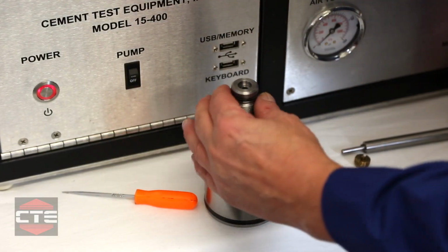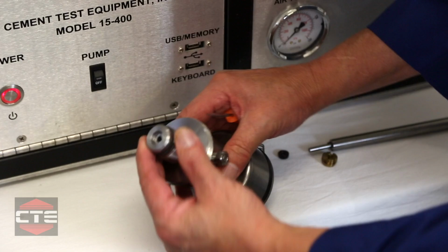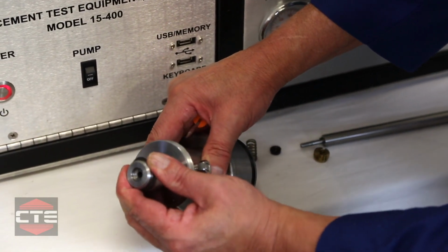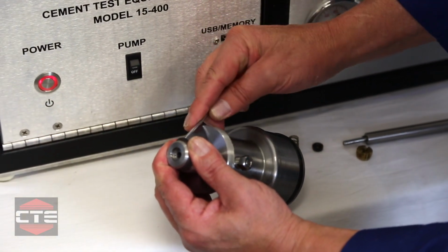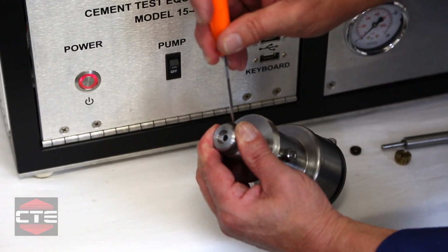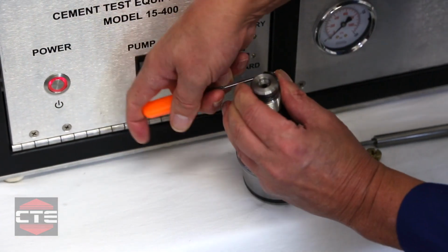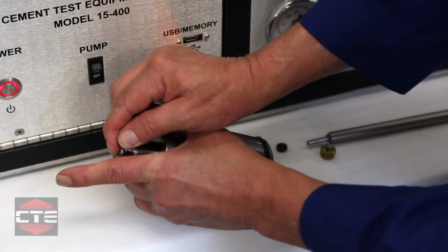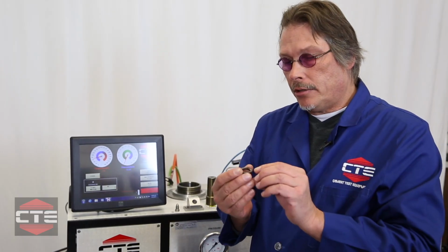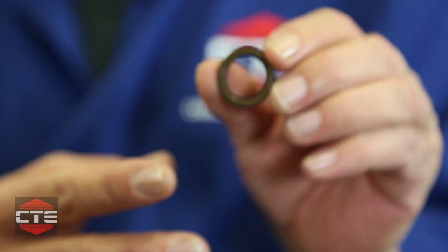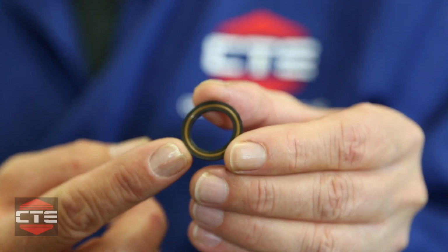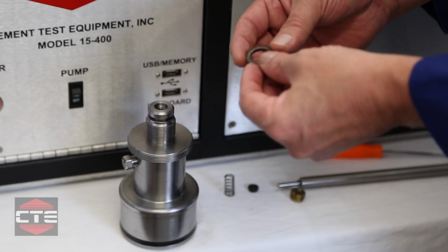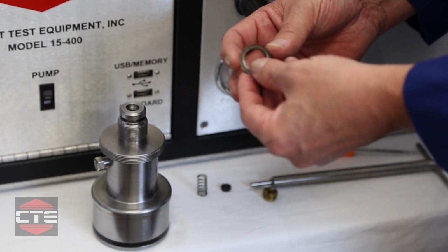To remove the 1067 poly pack, again, take your pick. If you apply pressure to the side, you'll get a gap on the side of it. You don't have to worry about harming the poly pack at this point because we are going to change it, and merely pry the poly pack off. Our new 1067 poly pack, as you can see, differs from an O-ring because it has this brown insert cut into the O-ring. What you need to remember about this is this brown insert always faces toward the pressure. So installing the poly pack, as I said before, the brown insert faces the pressure.